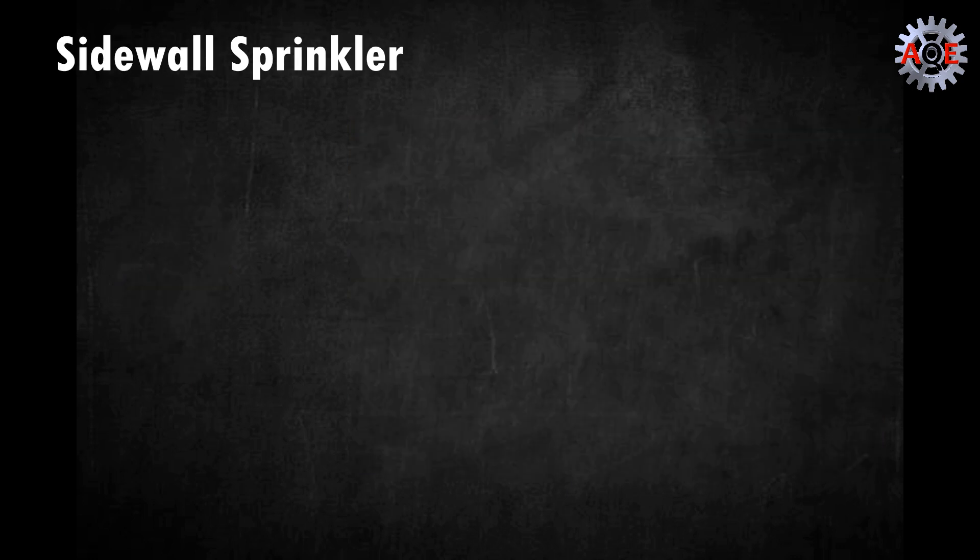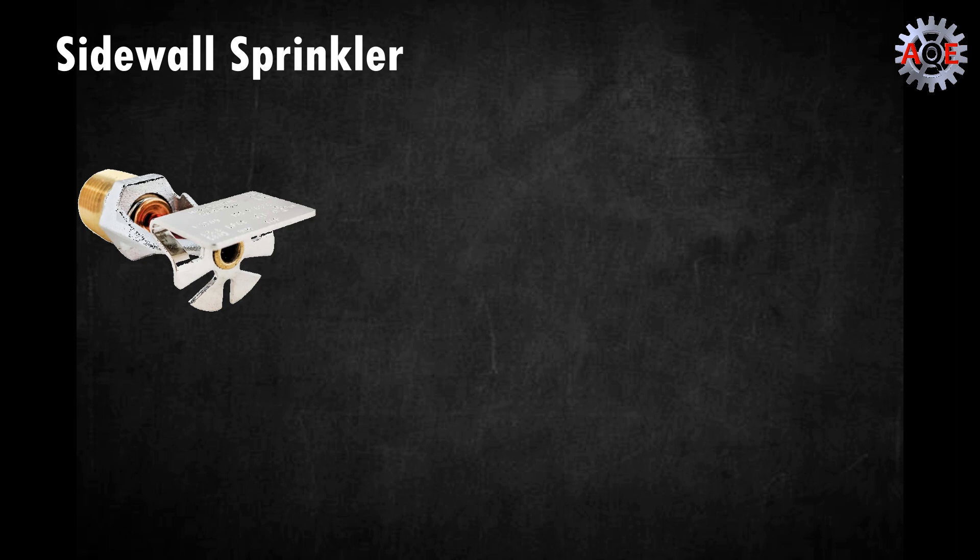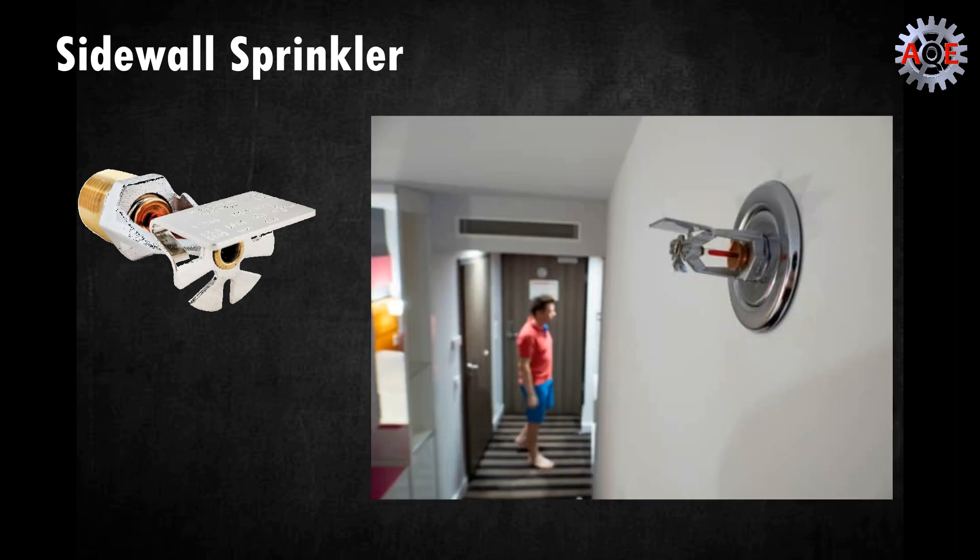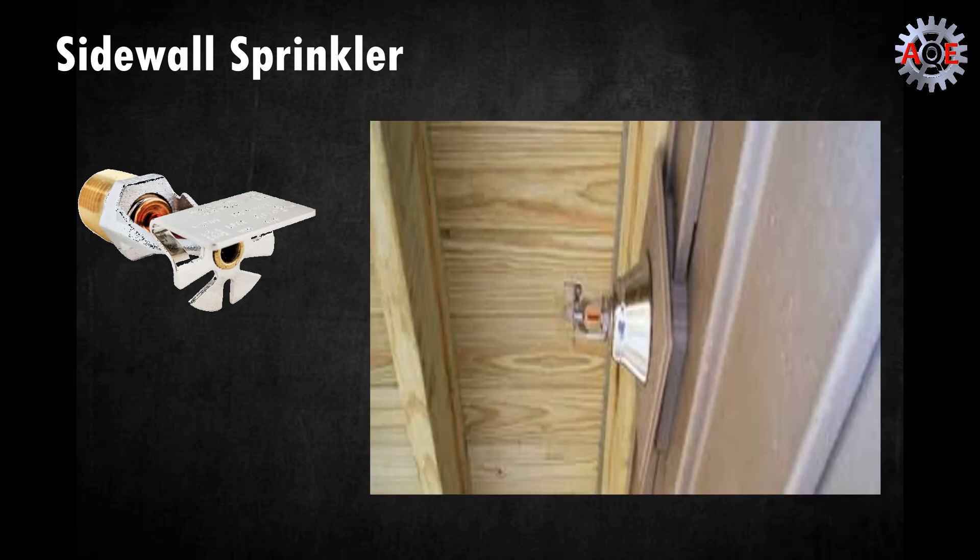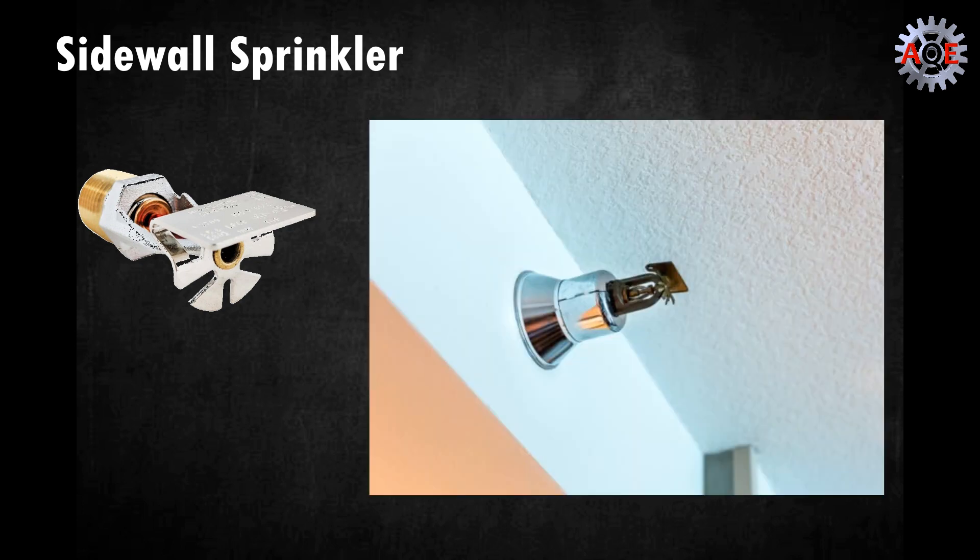Sidewall fire sprinkler heads are generally used in tight spaces such as hallways or small rooms. They only have half of a deflector so they can spray water in a half circle shape, which helps to cover the entire area. Generally, you will want to install sidewall sprinklers in the wall either along or under a beam.